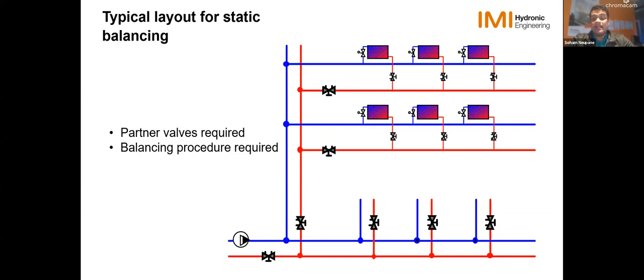And balancing with manual balancing isn't that easy. What comes into play is the interactivity. So think, you've got a system, you've got a hose basically that's connected to a common water outlet, and it has several outlets basically, and we all are holding the outlet of the hose. So if I go in and turn on the water, we all will start seeing the water flow, right? And that's the design condition. But what happens is, if someone else closes one of the outlets, you'll see more water coming out of the rest. And that's interactivity.